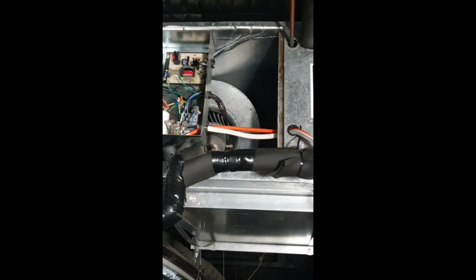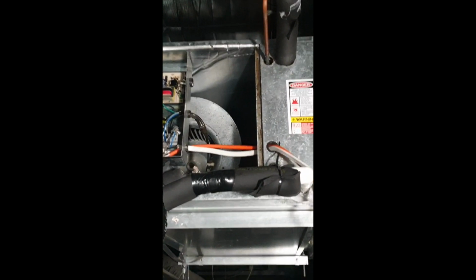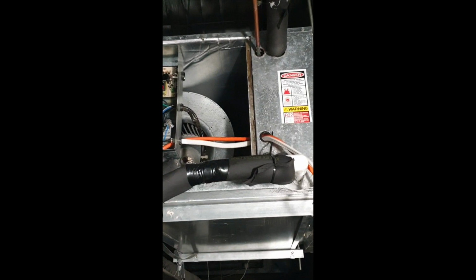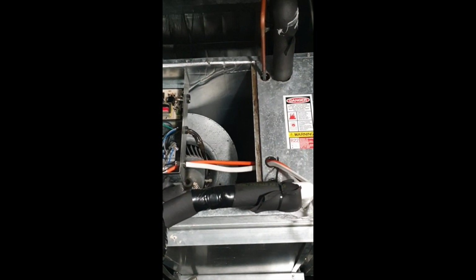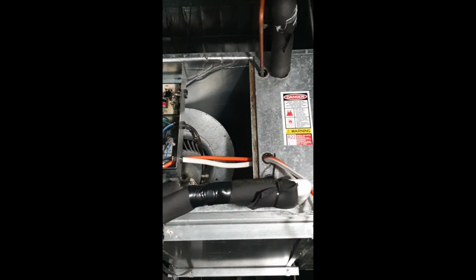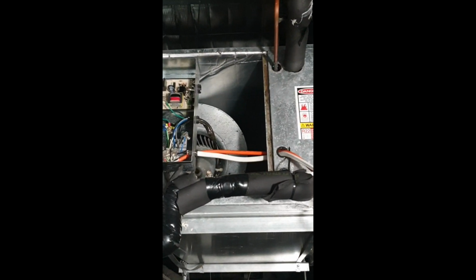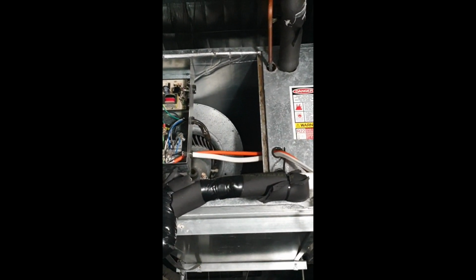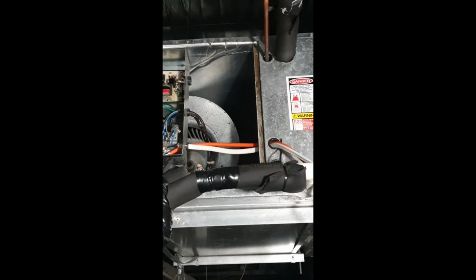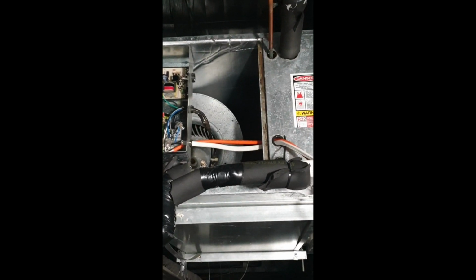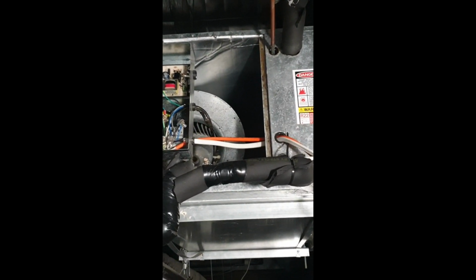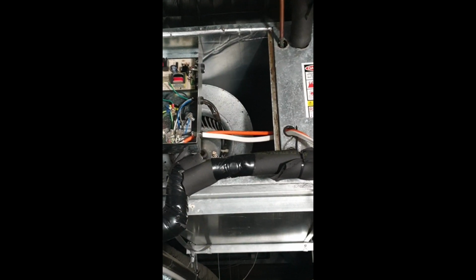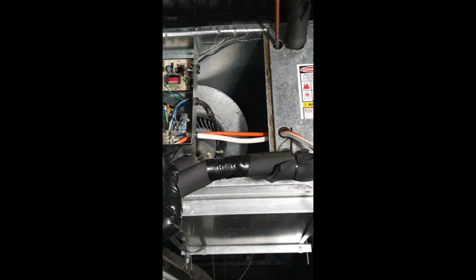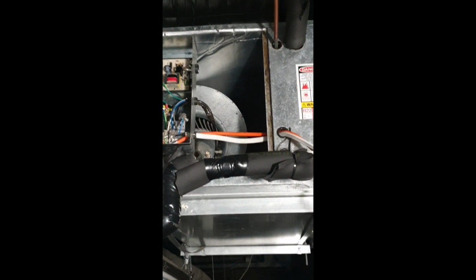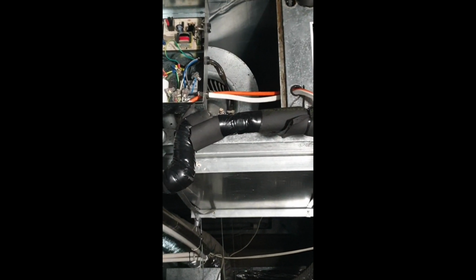Thank you. Hi guys, we're back in the ceiling space again. One point that is very important is that the indoor unit always requires a cold gas line going to it. That means that the expansion device is in the outdoor unit. Now these old Carrier Sundowner machines, the expansion device is actually inside the air handling unit in the ceiling space. We will need to cut out the capillary and insulate the liquid line. So this is really a worst case installation, not a big deal.